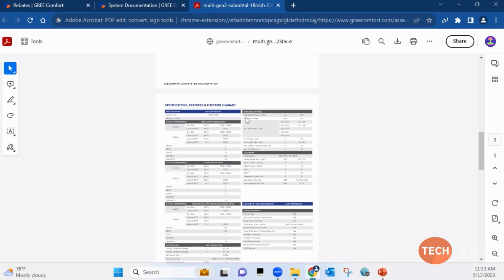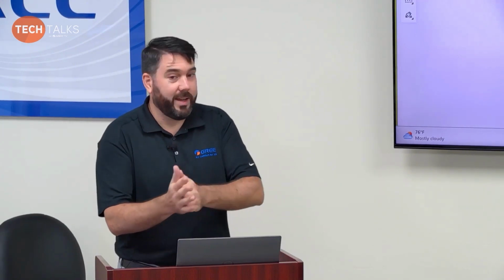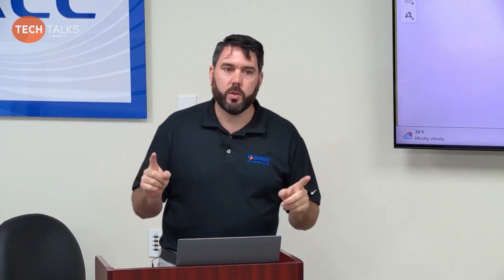You'll also have refrigerant piping info, so your additional charge amount, the pre-charge length, and the min-max. You'll notice the Multi-Gen 2 has 33 feet for initial pre-charge, and on max pipe length—the furthest indoor unit—you've got 66 there. Total pipe length is 131. The minimum is always 10 feet, not 9, not 9.5—10 feet. And that doesn't include the portion on the indoor unit itself, which is maybe 1.5 to 2 feet long; it doesn't include that.